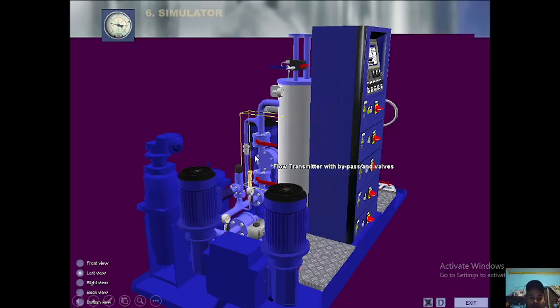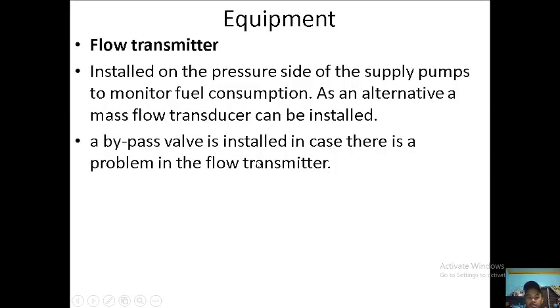Next, we have the flow transmitter with bypass, or the flow meter, so it measures. The flow transmitter is installed on the pressure side of the supply pumps to monitor fuel consumption. That is its main function. As an alternative, a mass flow transducer can also be installed. A bypass valve is installed in case there is a problem in the flow meter or flow transmitter.